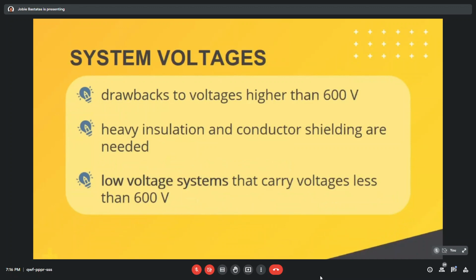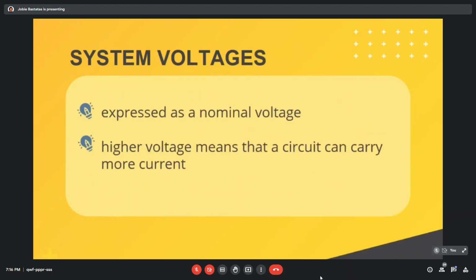System voltages. There are drawbacks to voltages higher than 600 volts because significant and costly special precautions, such as heavy insulation and conductor shielding, are needed. As a result, low voltage systems that carry voltages less than 600 volts are typically used in buildings. As I mentioned earlier, system voltage is expressed as a nominal voltage because it varies slightly. Design of a building's electrical system begins with establishing the desired building system voltage.